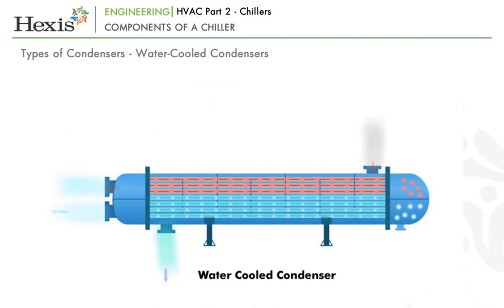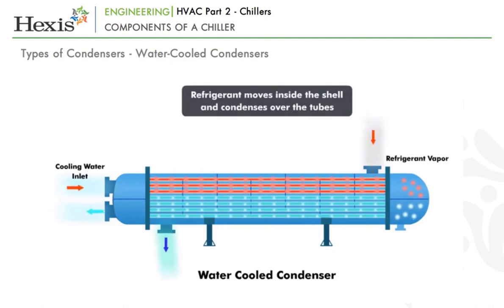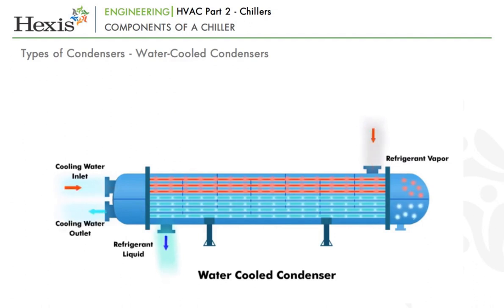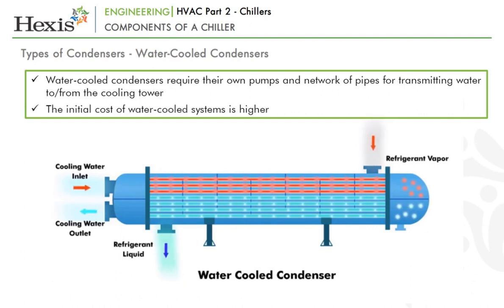In a water-cooled condenser, water is used to cool the refrigerant, and then the water is taken to a cooling tower to dissipate the heat gained. The cold water flows through tubes within the condenser, and the refrigerant moves inside the shell and condenses over the tubes, collecting at the bottom. In another variation, the refrigerant can be in tubes and the water in the shell. The liquid refrigerant is then taken to the evaporator through the expansion valve. Water-cooled condensers require their own pumps and network of pipes for transmitting water to and from the cooling tower, making the initial cost of water-cooled systems higher.